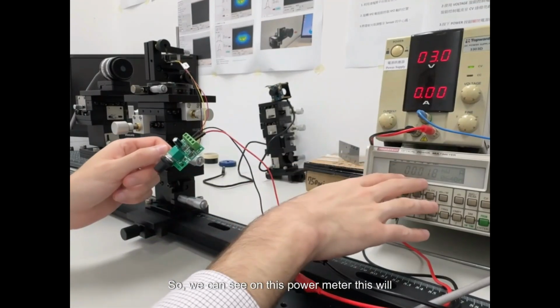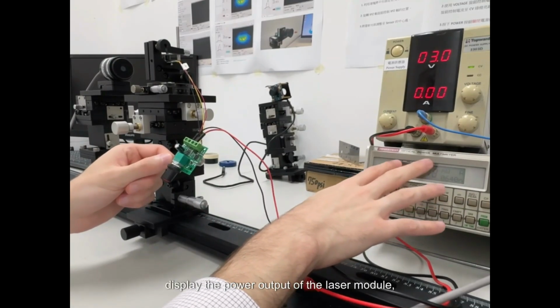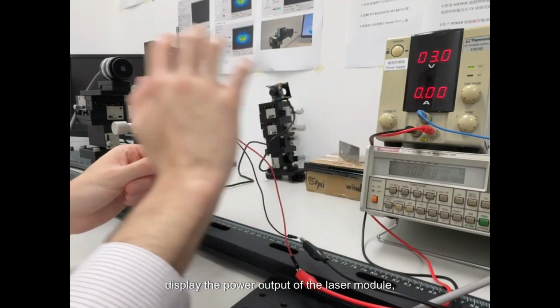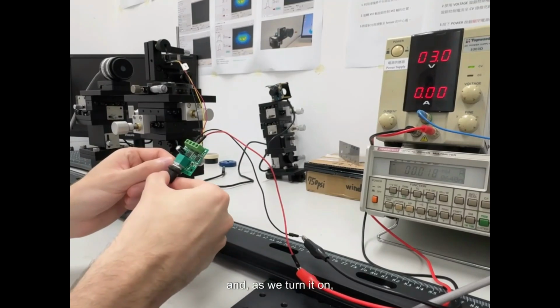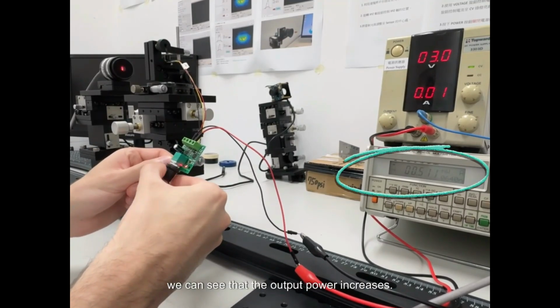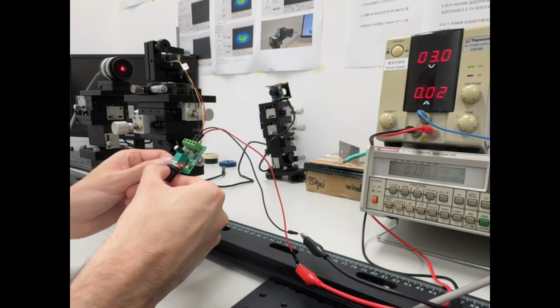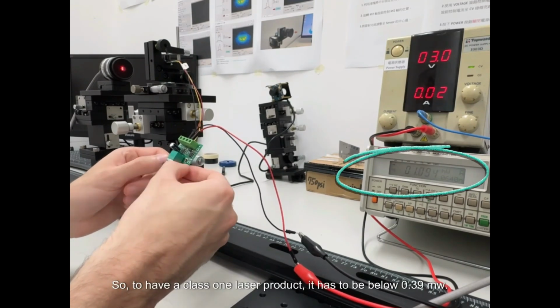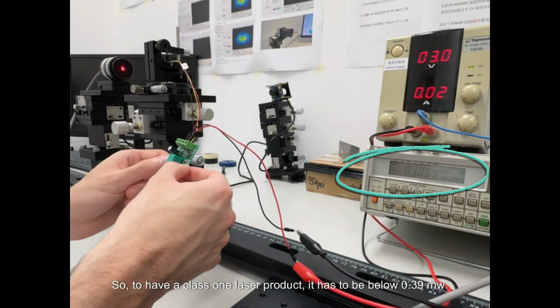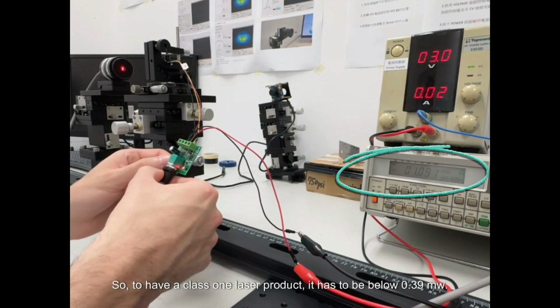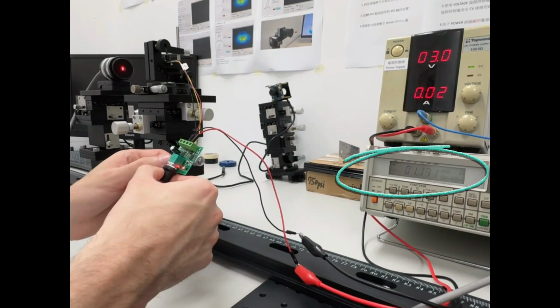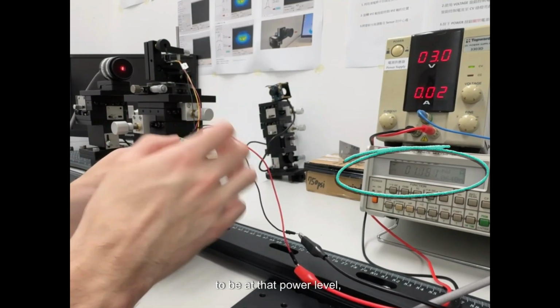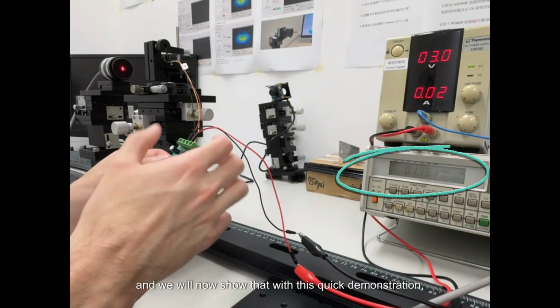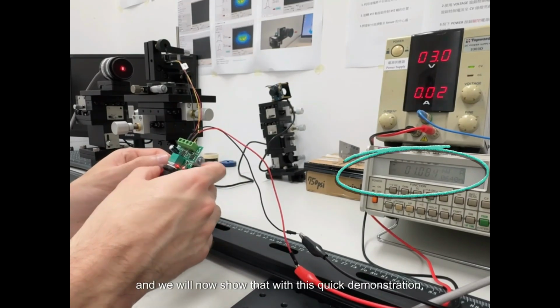So we can see on this power meter, this will display the power output of the laser module. And as we turn it on, we can see that the output power increases. So to have a class 1 laser product, it has to be below 0.39 milliwatts. However, this does not mean the laser itself needs to be at that power level. And we will now show that with this quick demonstration.